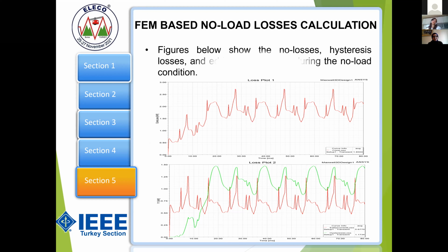Let's see the results of the simulation. Without any harmonic, we find that the overall losses of the transformer are 1850 watts. So we can see the different hysteresis losses and eddy current losses as well. As I told you, the hysteresis losses are more than 50%; here it is like 63 to 64% without any harmonics.